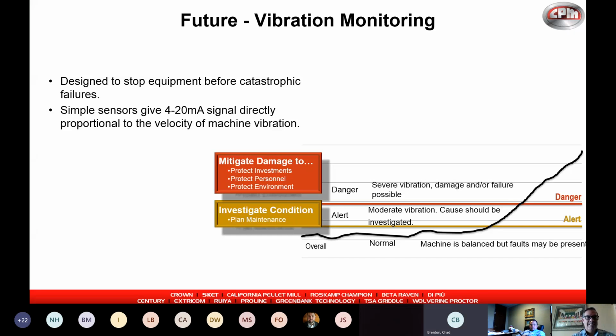One future idea we really like, and we'd like to see someone take control of it, involves vibration monitoring. Currently a lot of people use a sensor that gives the overall vibration of a machine, which is great - it gives an analog signal saying vibration is normal, now it's getting a little high, now we're in a danger zone, we need to look at that machine. But it doesn't pinpoint exactly what's wrong or what's causing that vibration.